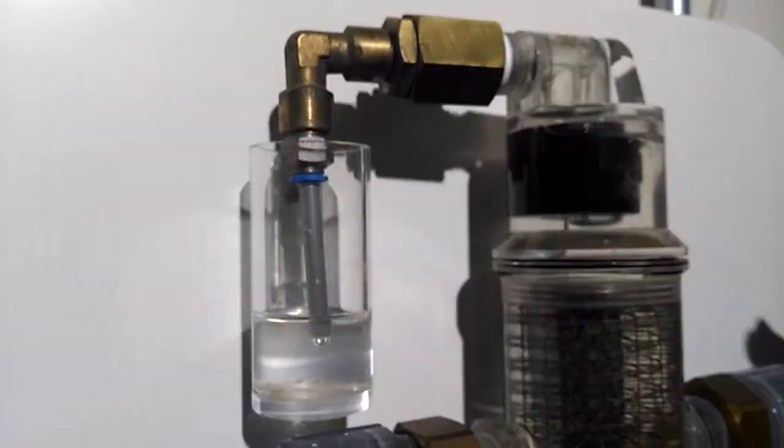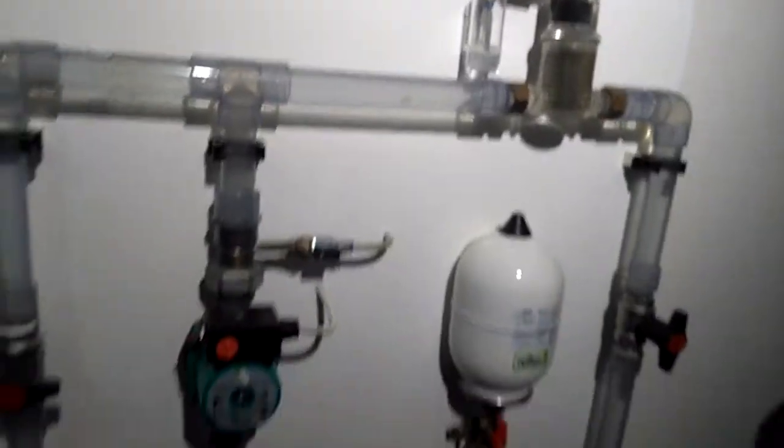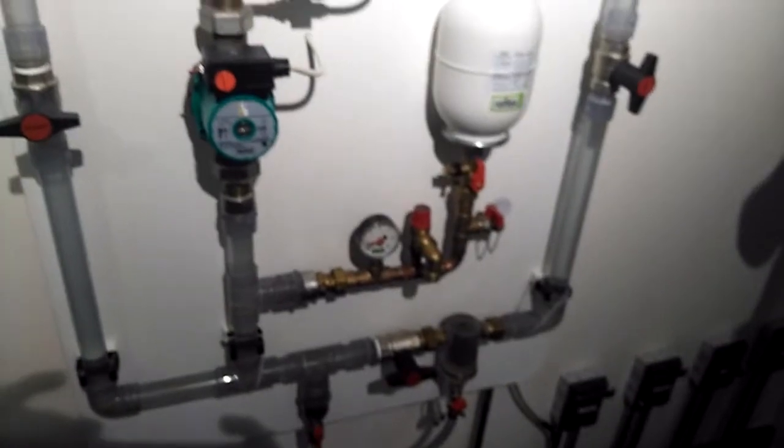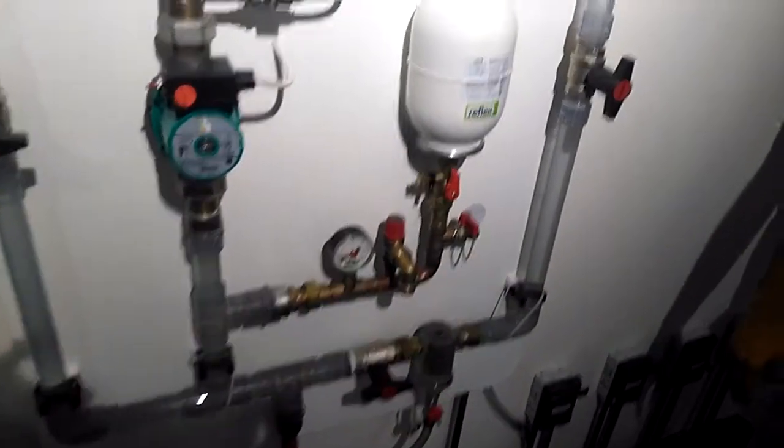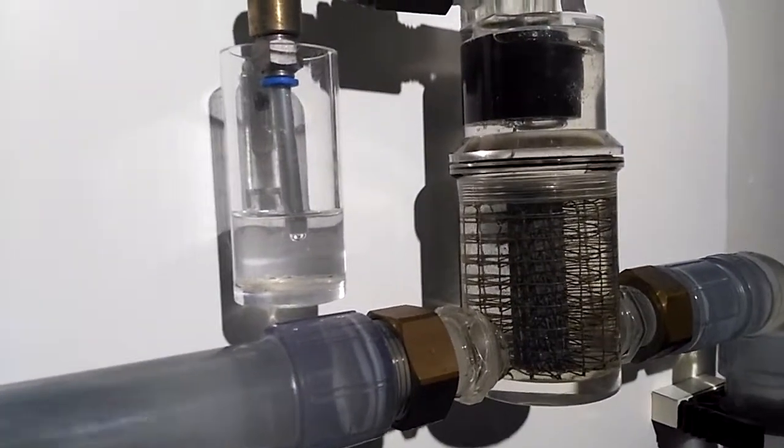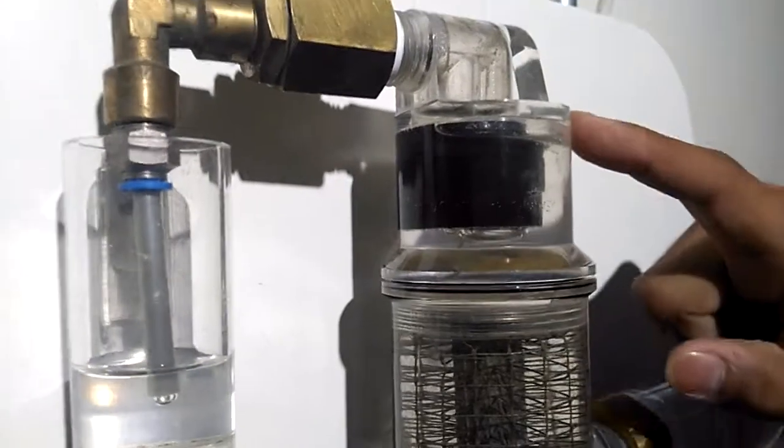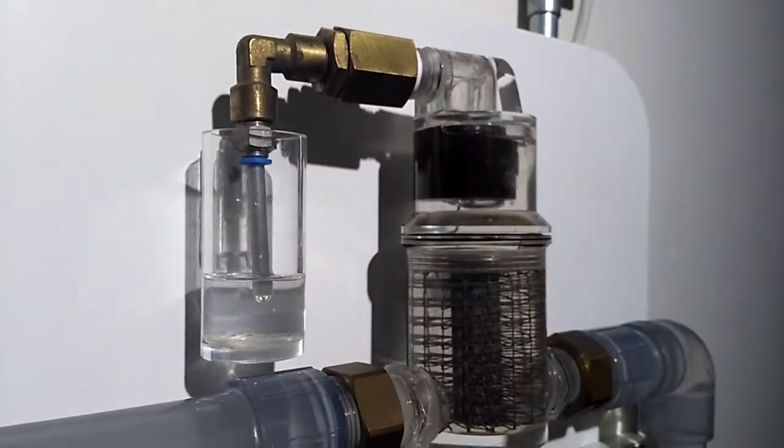We can eliminate air bubbles up to 5 microns size, even dirt particles up to 5 microns. You can see small micro bubbles - they go slowly to the top and accumulate in a big space.